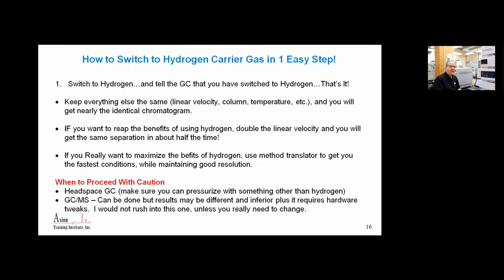Here's my how to switch from helium to hydrogen in one simple step. My statement is make the switch. Simply switch the gas from helium to hydrogen. When you make that switch, tell the GC that you made the switch. A modern GC uses that information to calculate pressures and flows. It must know what your carrier gas is. It uses that viscosity to know what pressure to apply in order to get the correct flows. What you'll notice about hydrogen, one of the many advantages is that it has much lower viscosity than helium, which means we can operate at lower pressures and still get higher linear velocity.